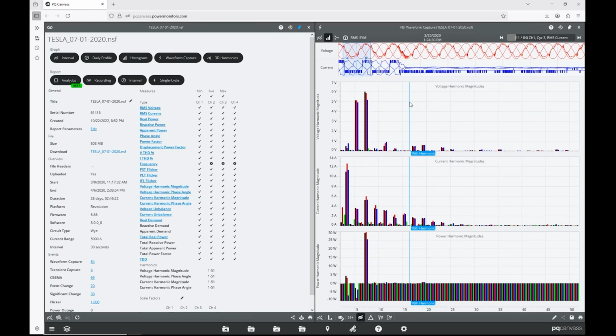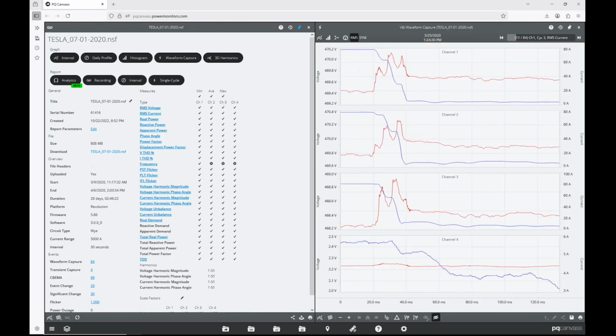And in general, any three-phase nonlinear load is usually fifth and seventh harmonic, and then you'll sometimes see other multiples of 6 plus or minus 1 as you get higher. But here, fifth and seventh is by far the dominant. So on a feeder level, those are the two harmonics you want to look out for. And you'd also want to look out for resonances, which are very common at 300 hertz, which is the fifth harmonic. And then these are mostly RMS events.